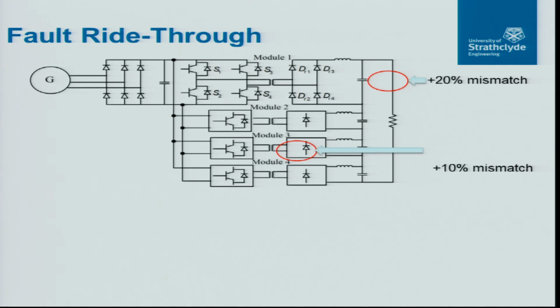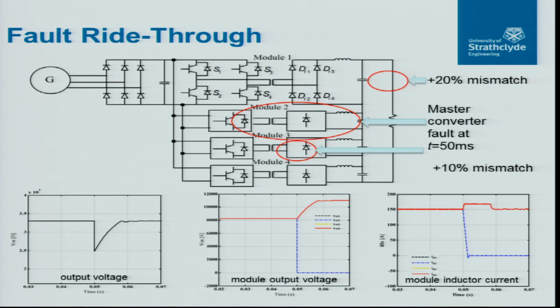So we're looking at levels of mismatch here. We then fire a fault on the master converter, and we see here a dip in the output voltage. We see the output module voltage is taken down to 0 here, and the other ones step up to take over. Module inductor current, so that you've got to balance for the new voltage, the control loops activate to increase the current in each of those output inductors to drive up the output current and drive up the output voltage.